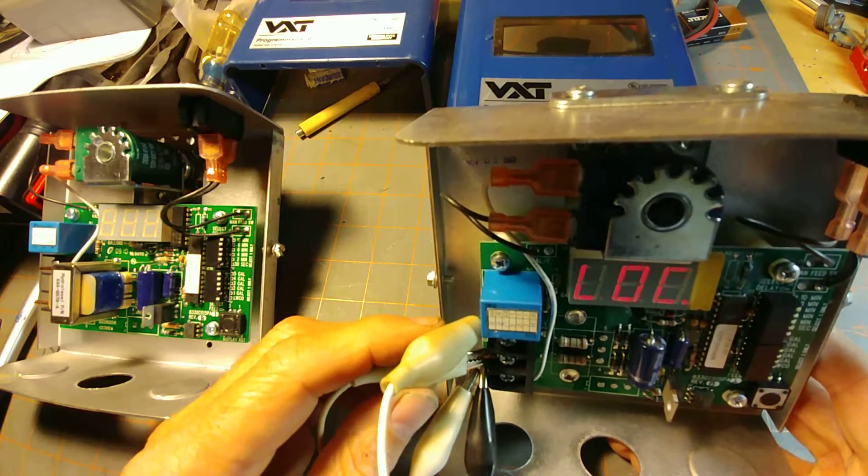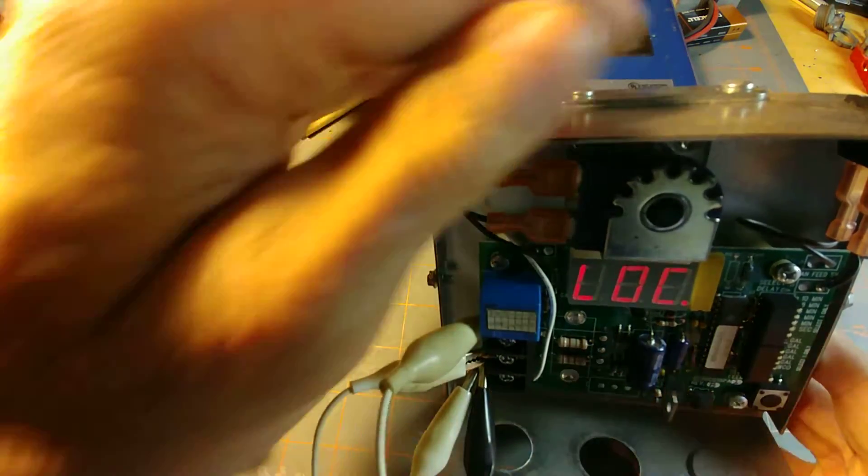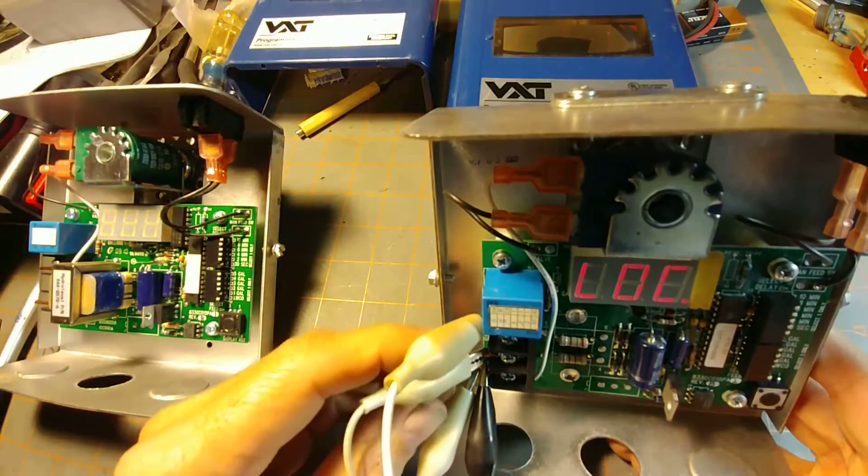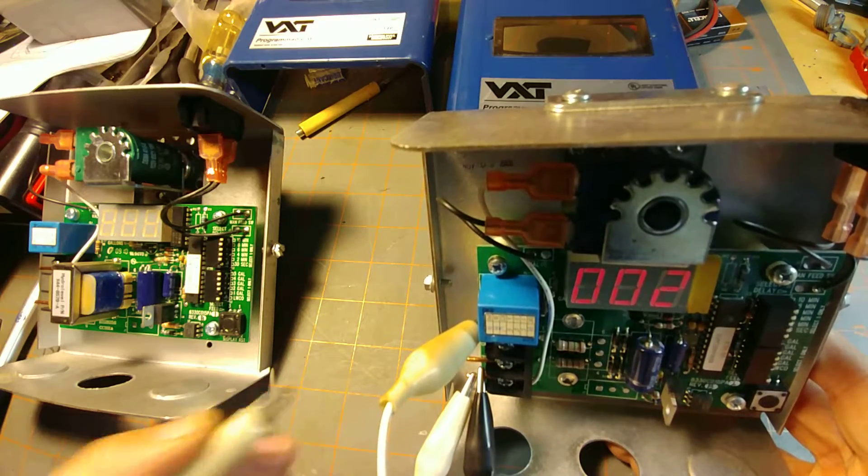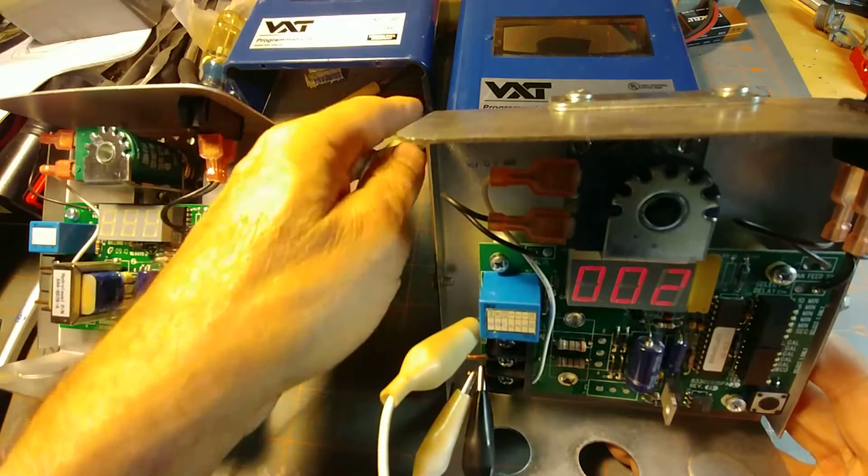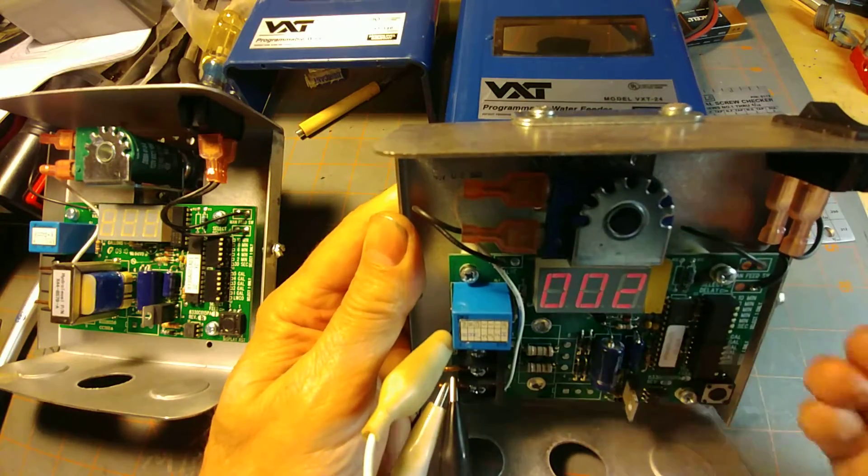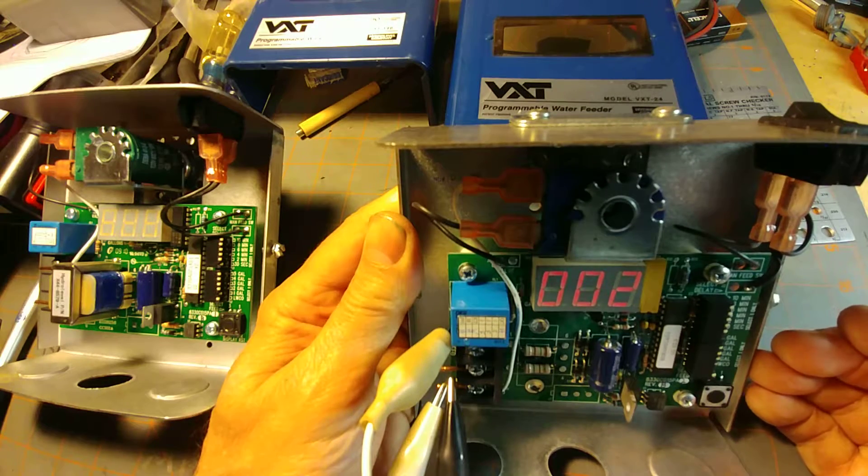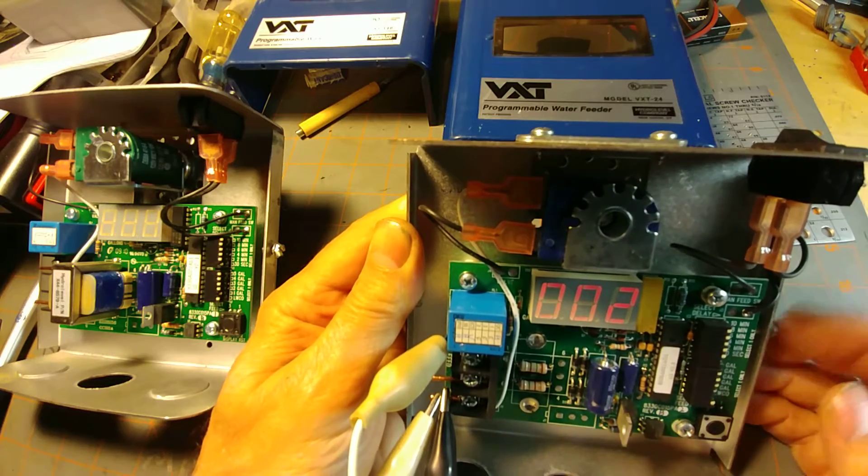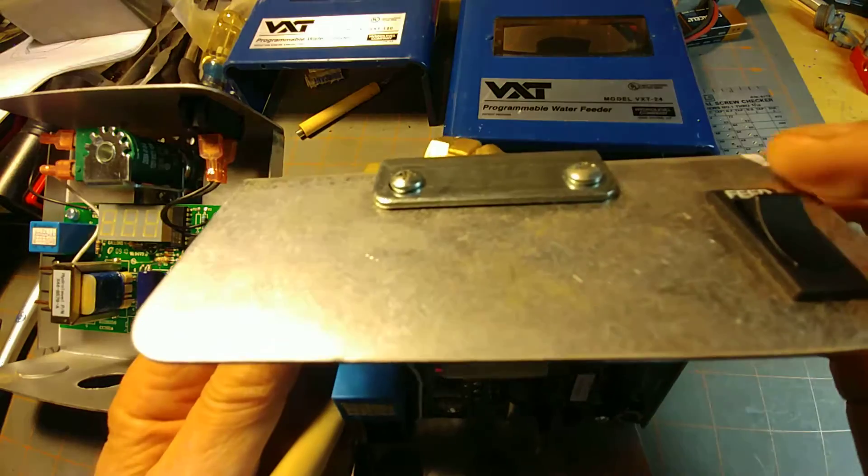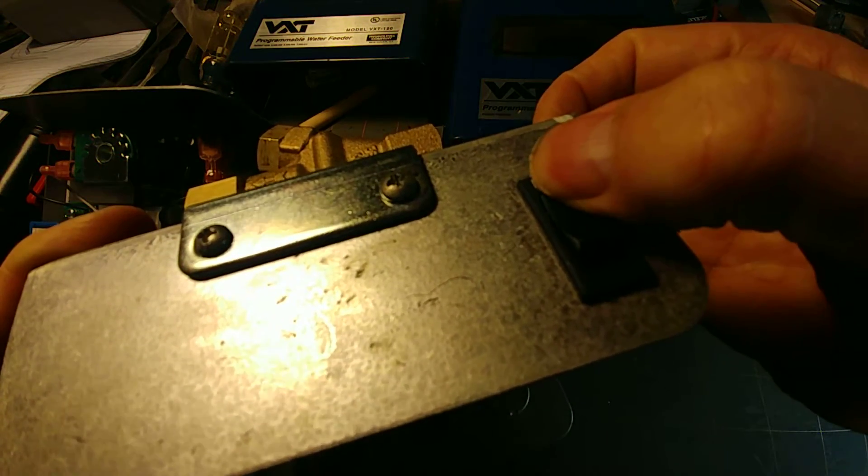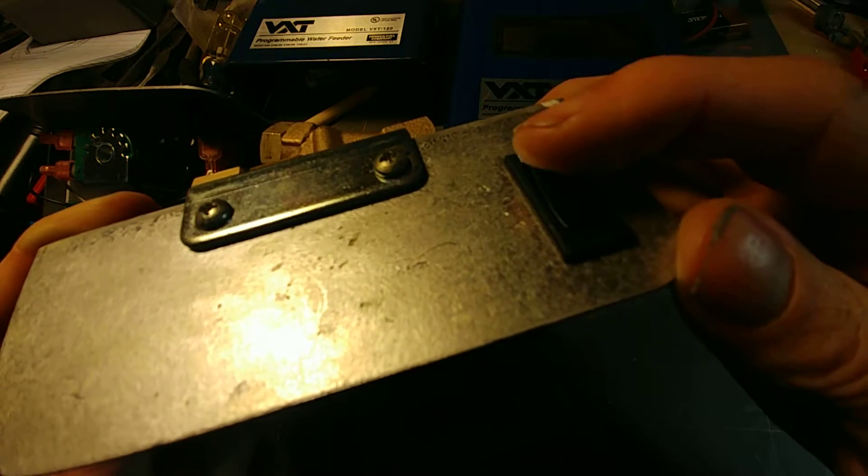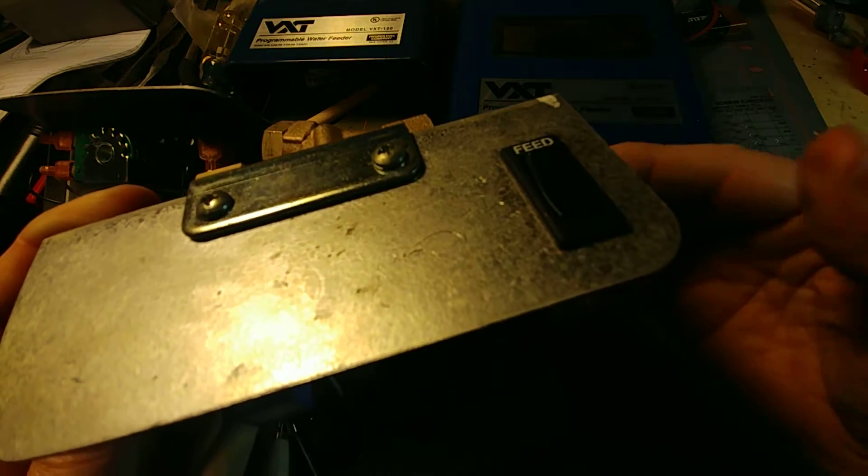In order to clear that, you either de-energize the system or reset. That clears the fault, clears the lockout. And now you see the number two, just like you saw originally when the unit was first energized new out of the box. The other way to feed water electrically is to push down on this feed switch here. The nice thing about that rocker switch is that once you release the pressure, it stops feeding.